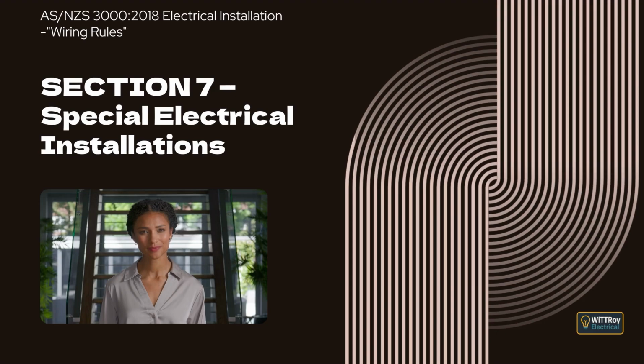Clause 7.2.6.1 General. This clause explains that fire and smoke detection and alarm systems include fire and smoke detection equipment, fire indicator panels, fire and smoke alarm systems, and warning and intercom systems. The key idea is that all of these elements together form the safety service responsible for detecting fire and alerting people. Clause 7.2.6.2 Wiring systems for fire detection and alarm systems. This clause introduces the requirements for wiring systems that supply fire detection and alarm systems, focusing on maintaining supply and system integrity under emergency conditions.